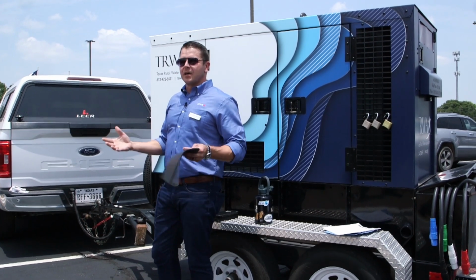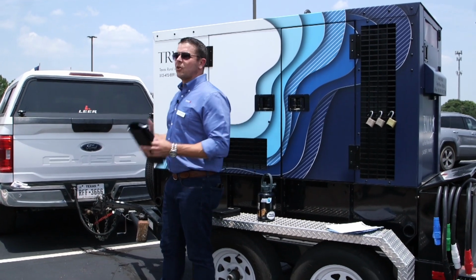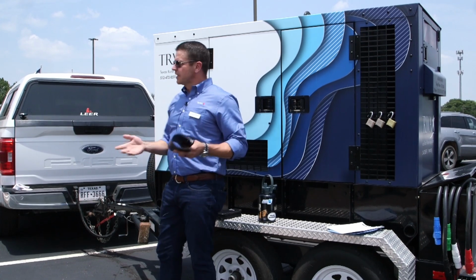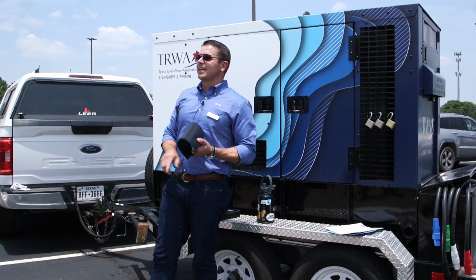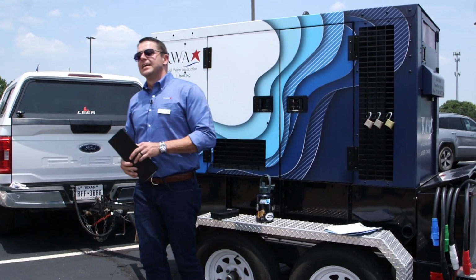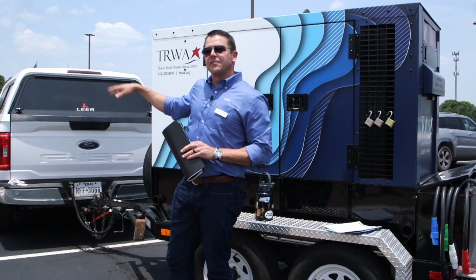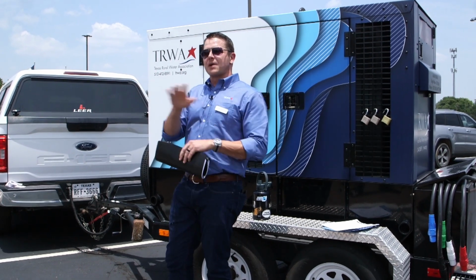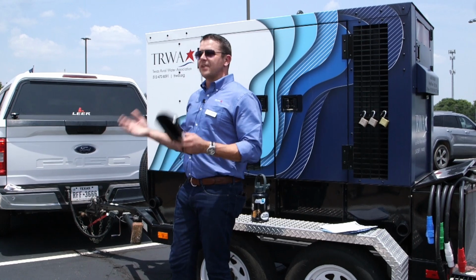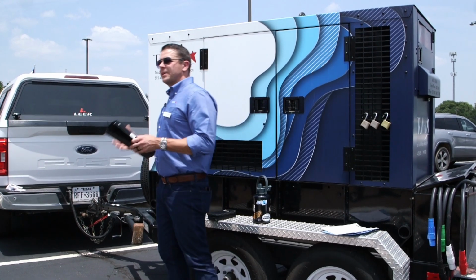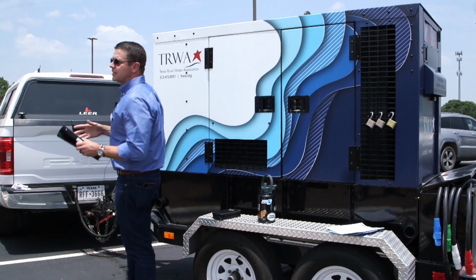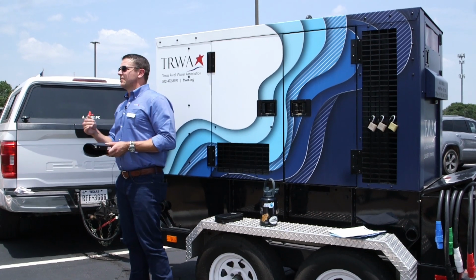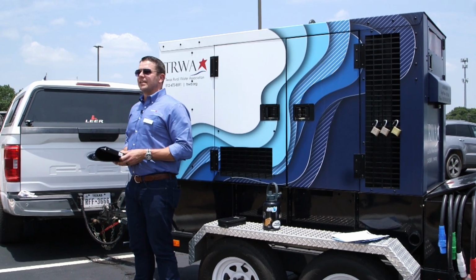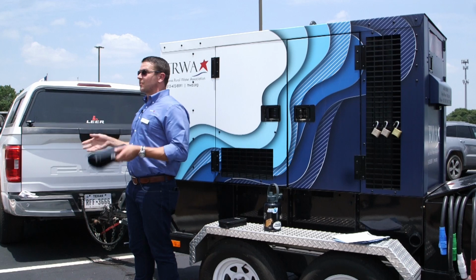We do emergency response, so whenever we're called out, we ship these all around, typically in the coastal area, but we've been called to hurricanes, fires, floods, things like that. We use the little small one in here with the VFD because we transfer single phase power from the generator to 3-phase, so we get to run smaller applications or even larger applications, but at maybe just a percentage of the actual run. So at least we get some things moving, specifically for lift stations.